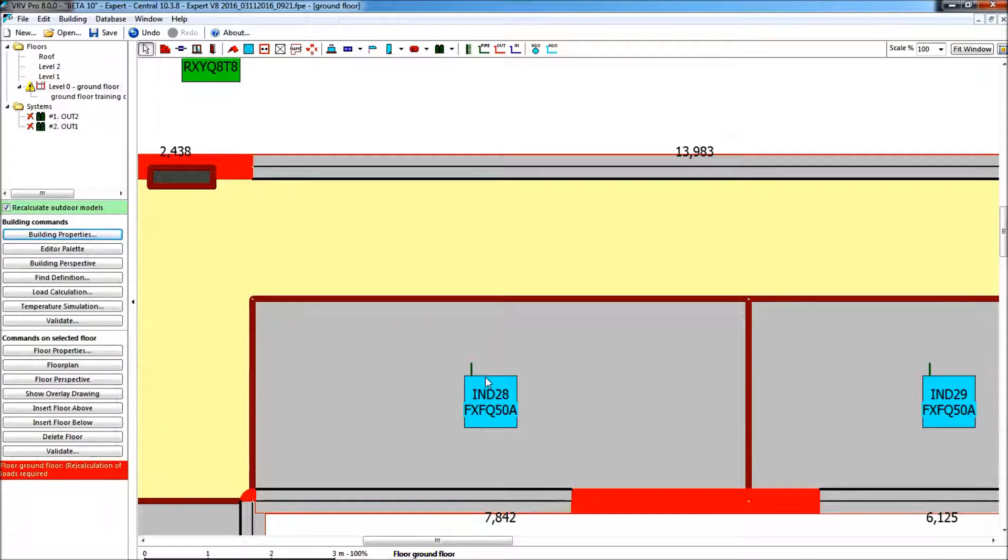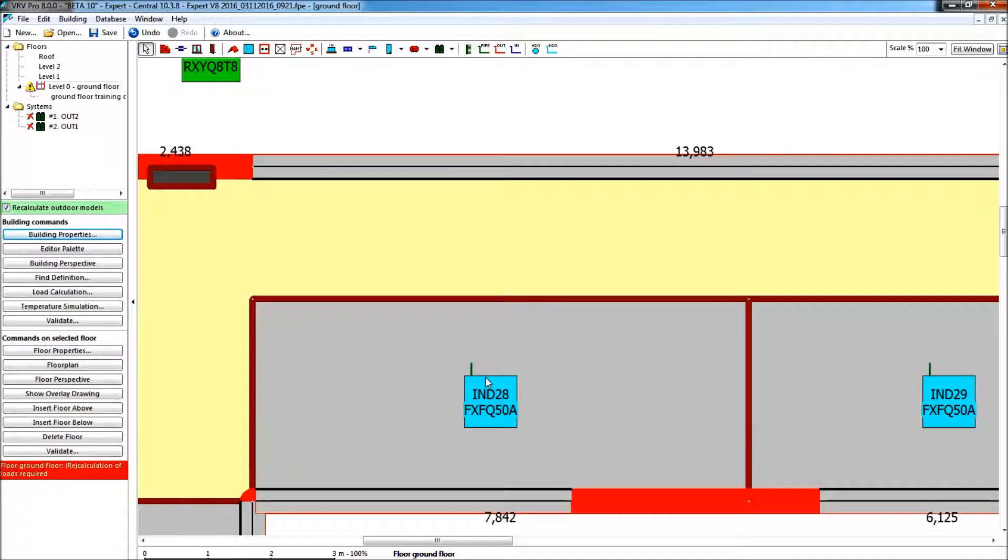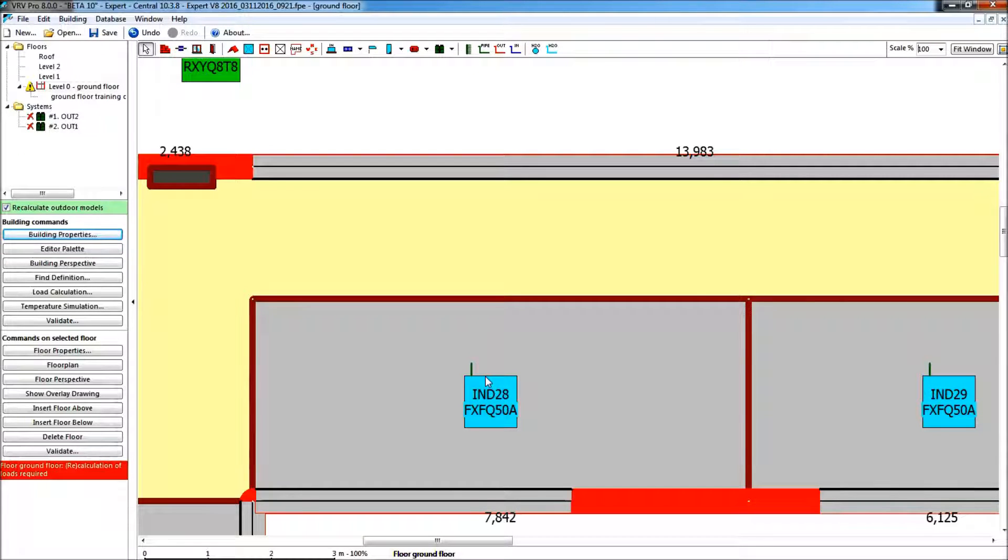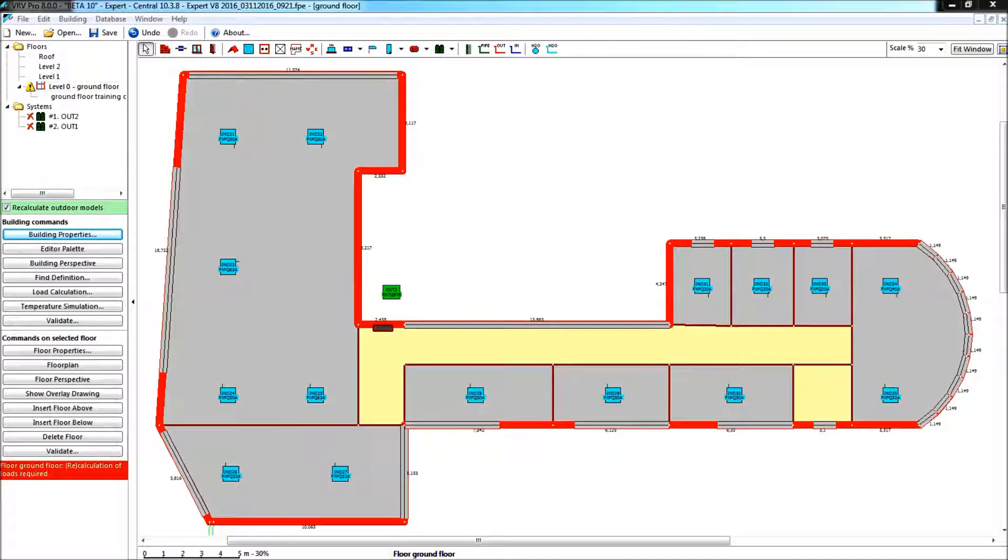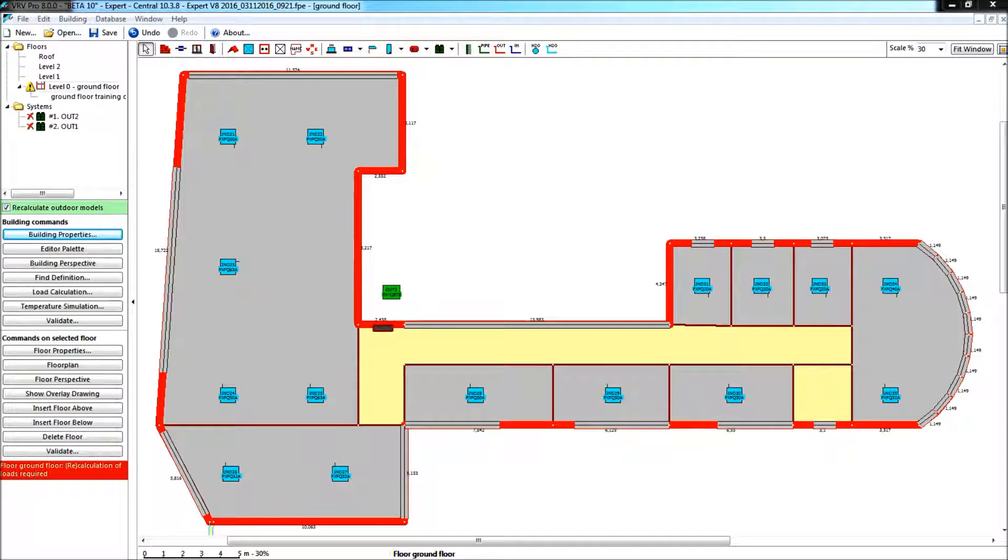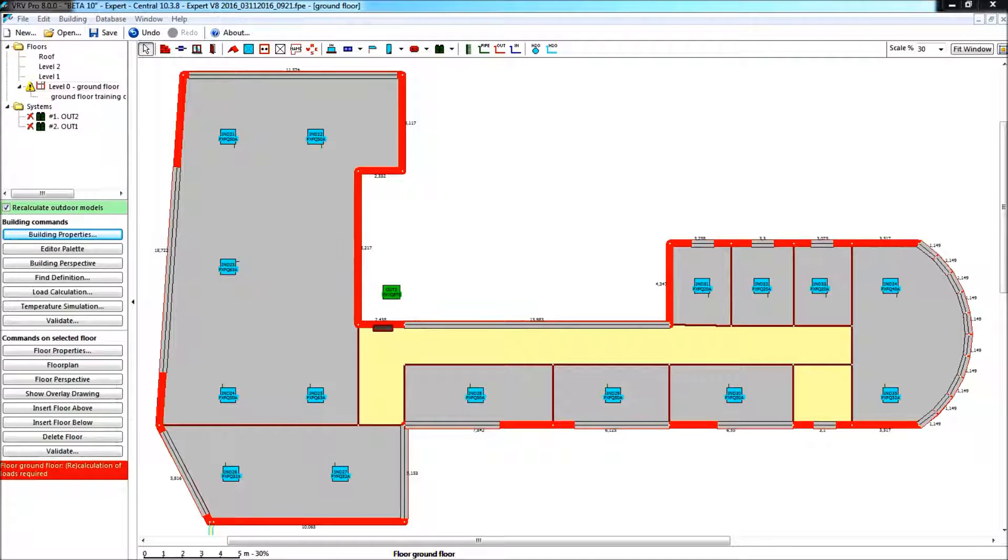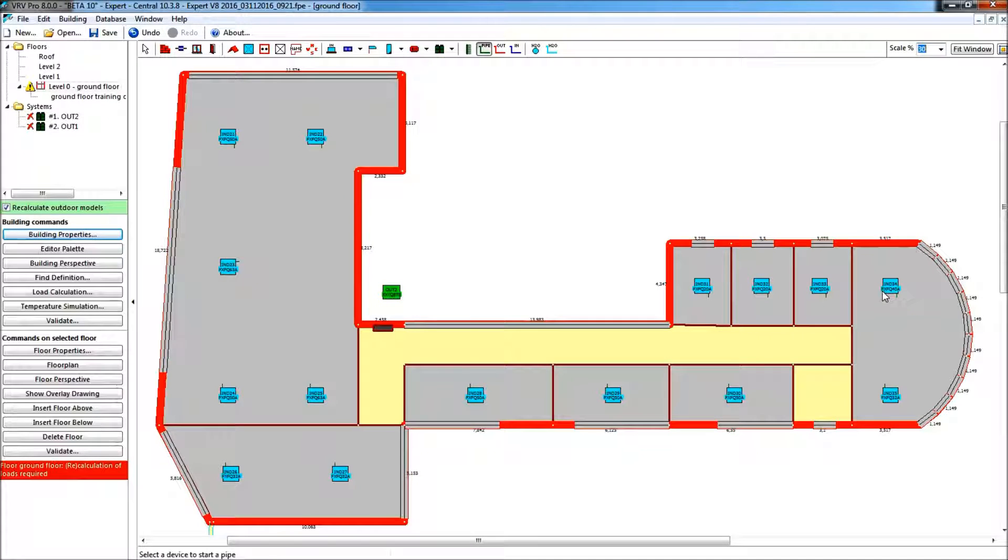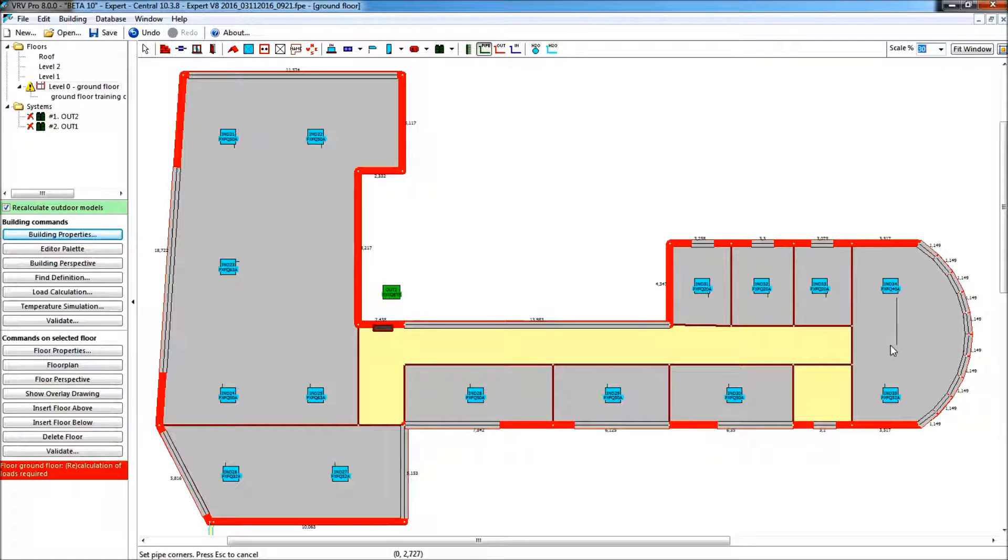This allows us to set the correct rotation of the indoor units right away. Nevertheless, when you are drawing a pipe, still stick to your habit to start drawing from the middle of the unit towards the main piping. So drawing that main piping, like we already said in the teaser email that we sent you a couple of days ago, we said that we would need to connect the most remote indoor unit to the shaft or outdoor unit first.